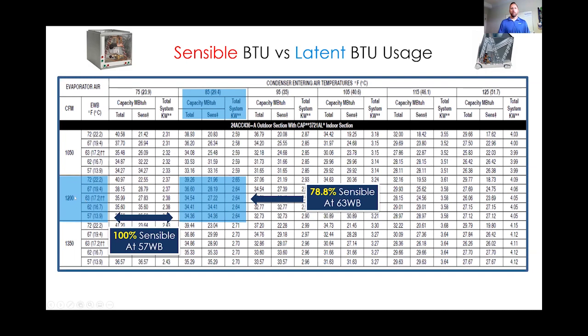So here is what the manufacturer is stating. They're stating at this design parameter at 63 degree, entering wet bulb, which by the way, if I had it on the bottom here, would say 75 degrees and 50% relative humidity. That's what it would tell you. That this total BTU capacity is 34,540 BTUs. 27,220 of those BTUs are just changing temperature. So that is cooling the air. The rest of the BTUs is trying to remove moisture. If we have an ancillary system that can remove the moisture, my air conditioner is going to be able to do a much more effective job at lowering that temperature. Mm-hmm. Cool. Thanks for clarifying it.